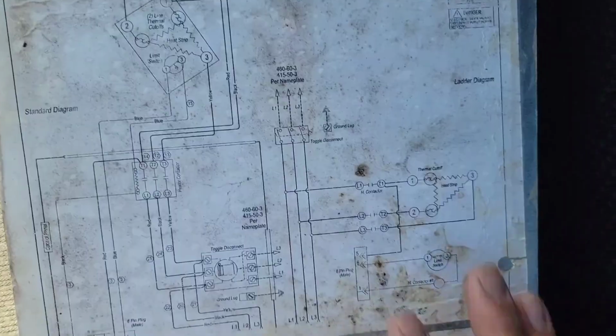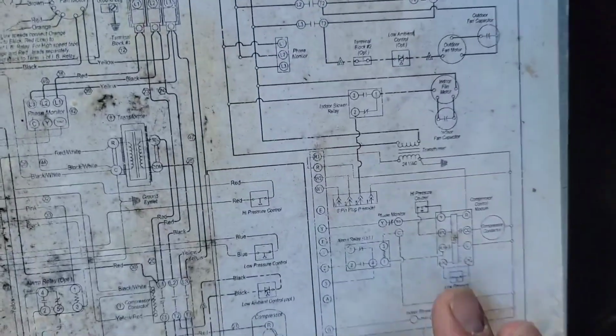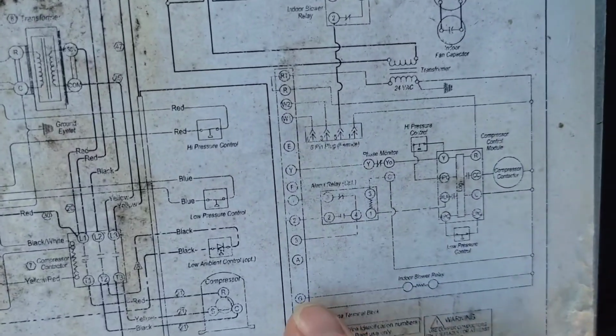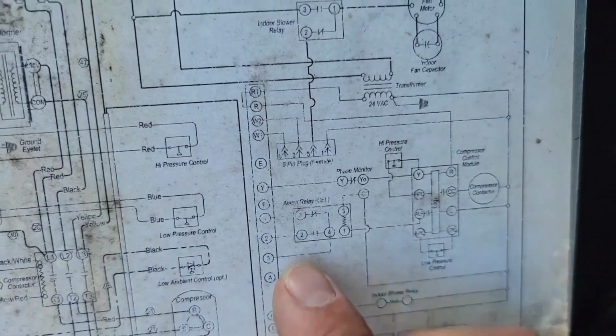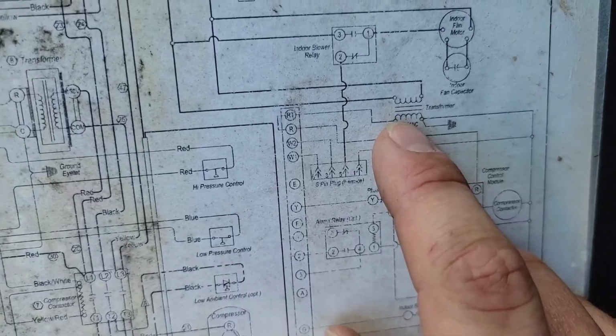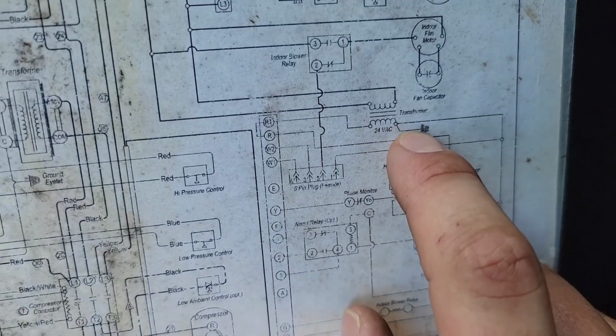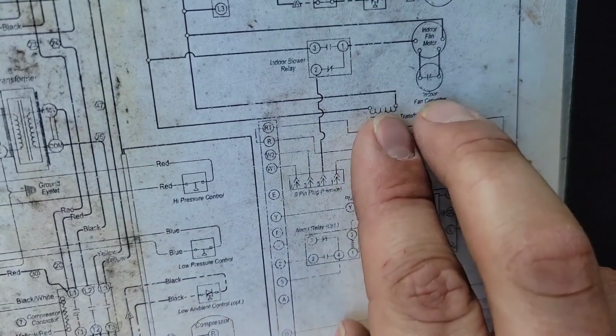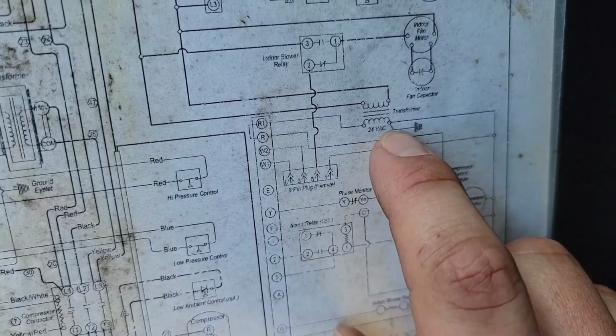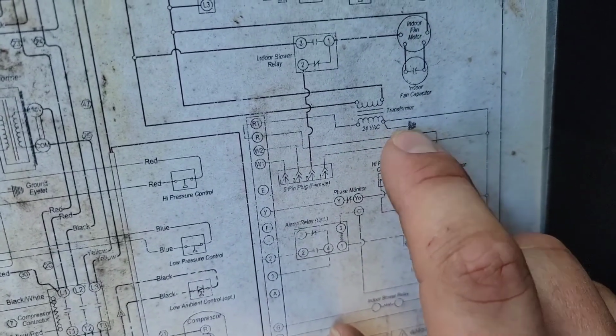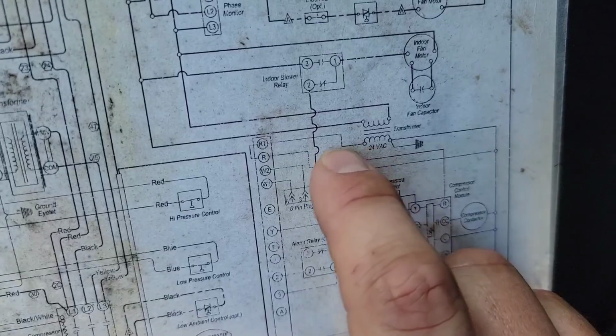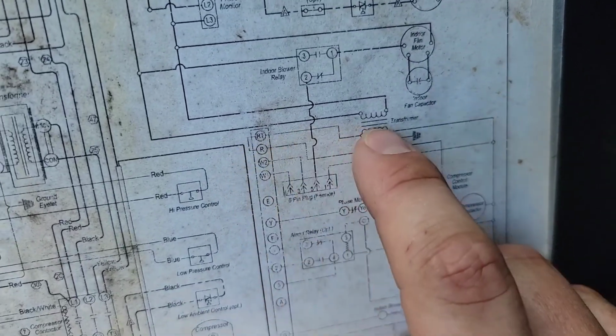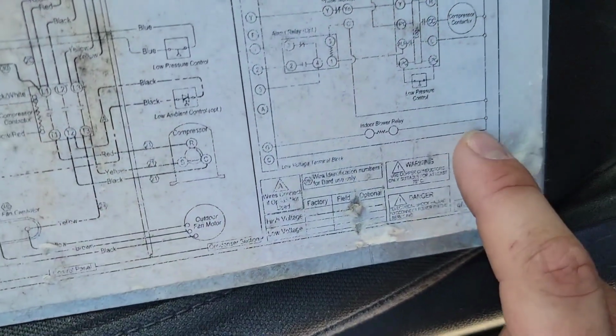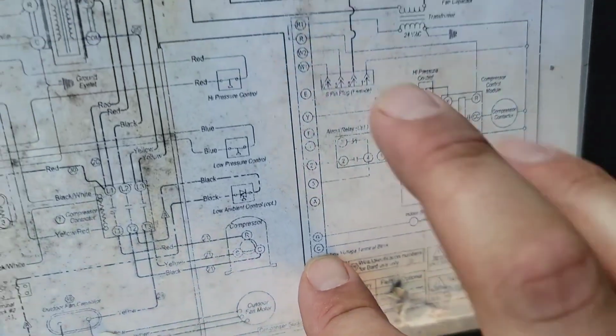Okay. Let's go over the schematic. For those of you that need to learn more about reading schematics, you've got your low voltage wiring here. Let's go over the secondary of the transformer right here. We've got our C and our R. That makes our 24 volts. So you can see how the C is connected to the ground. Right there, that means ground. This side is R, so red. And then if you follow this line down here and over, that's C. So C and R, 24 volts.